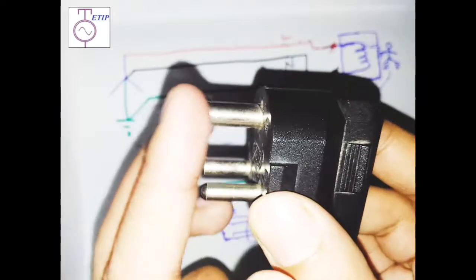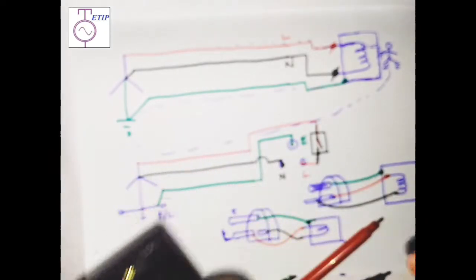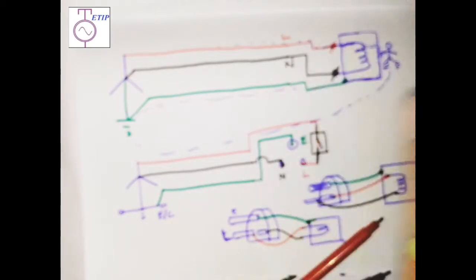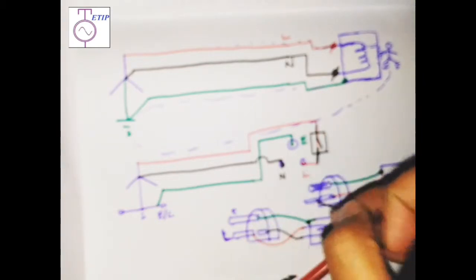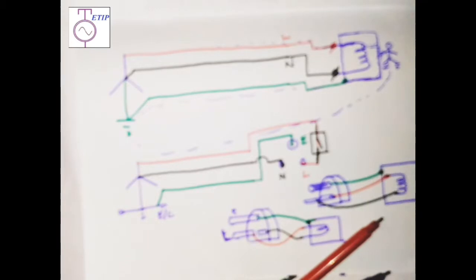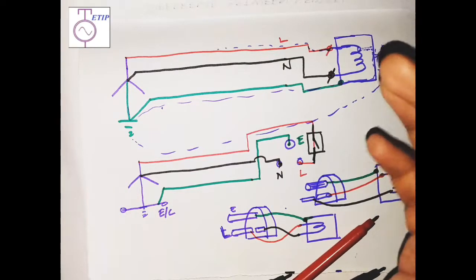Now let me show some typical features of the socket. If you look at the plug pins, the earthing pin is thicker and longer than the other two pins. A thicker earthing pin causes lower resistance. Because it is longer, it is inserted into the socket first — meaning whenever you plug in the equipment, the body is earthed first before the power supply becomes available, discharging any stored charge before energizing.